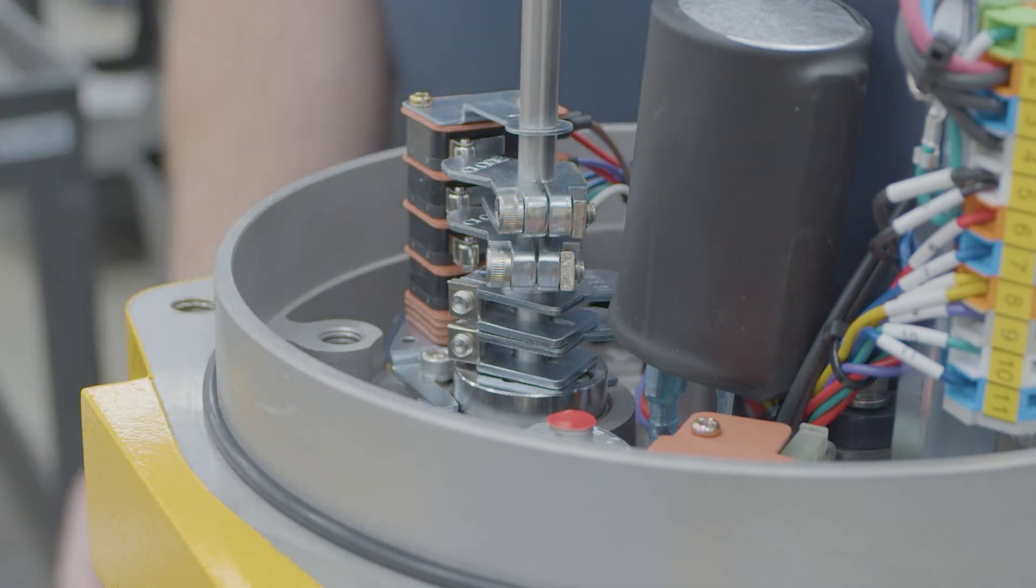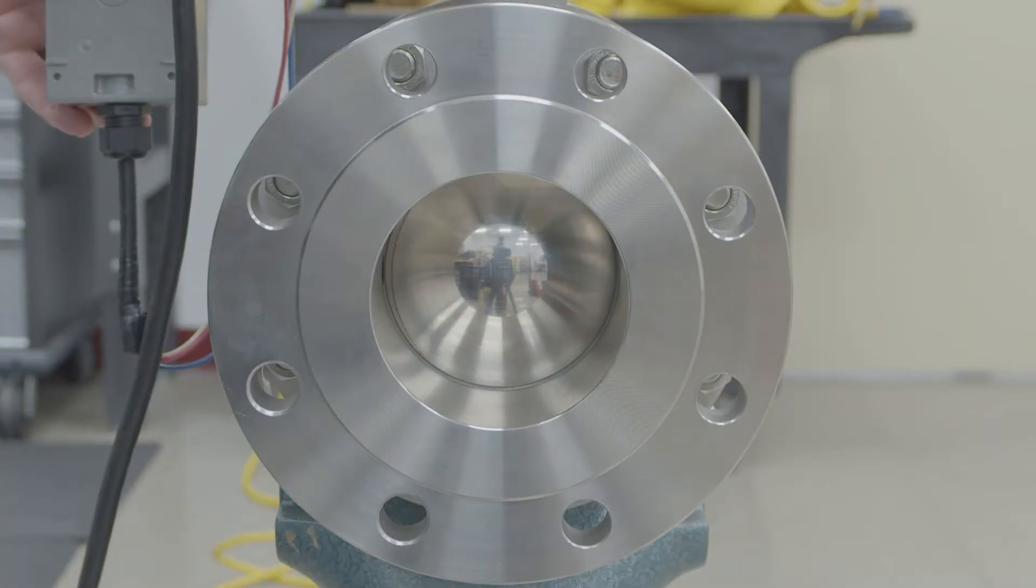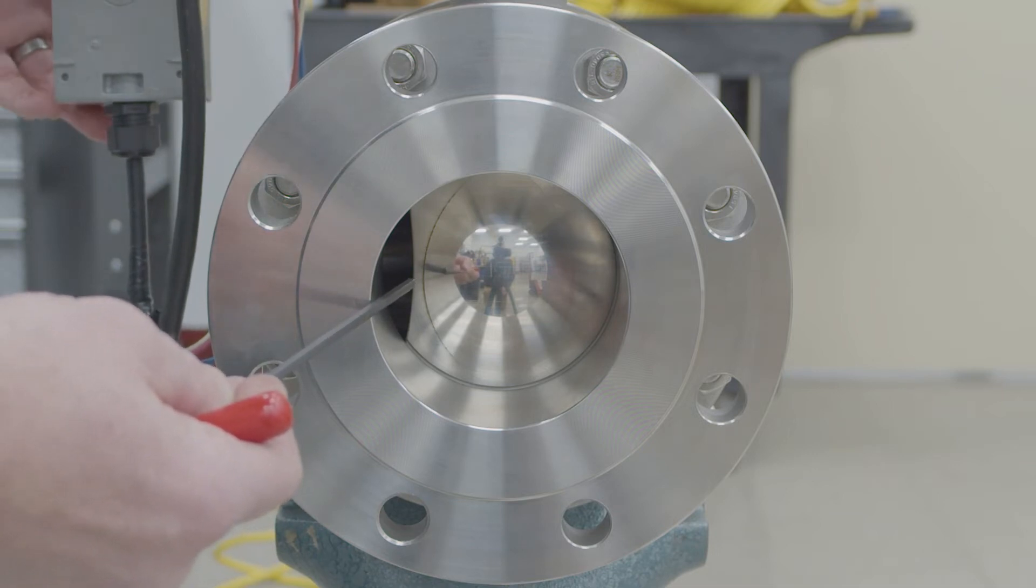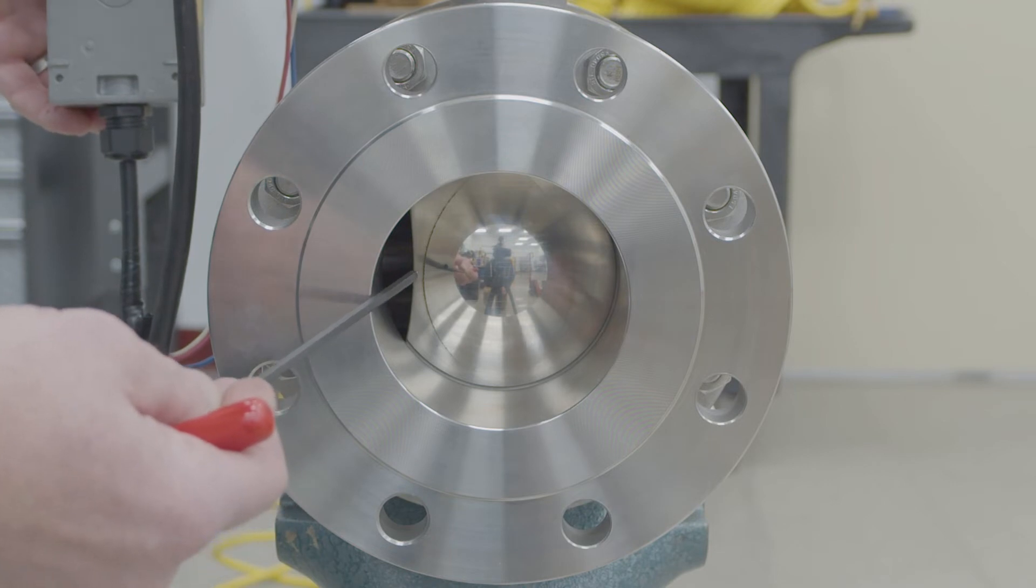So first thing you do is look to see where it's at. And you're going to look for like a dirt line on the ball that will show you how much your seating area is. So that tells you you have, you know, roughly three sixteenths of an inch of seating area. So that is good on a four inch size valve.